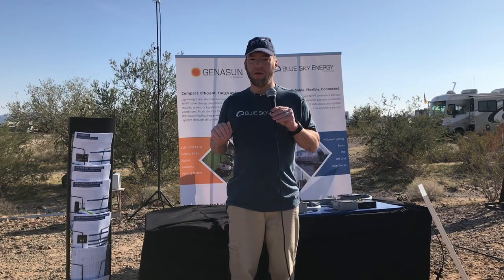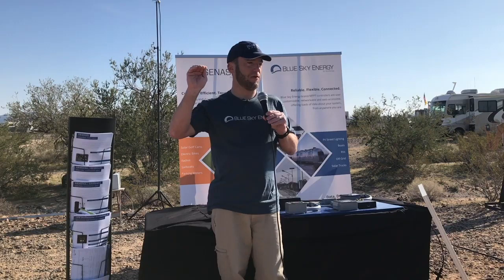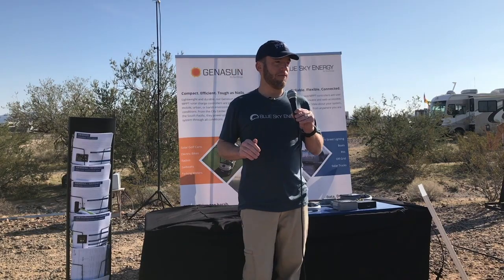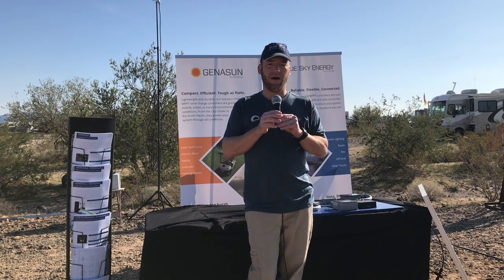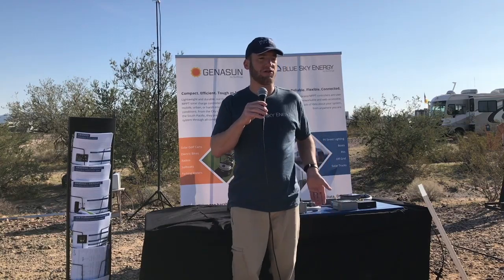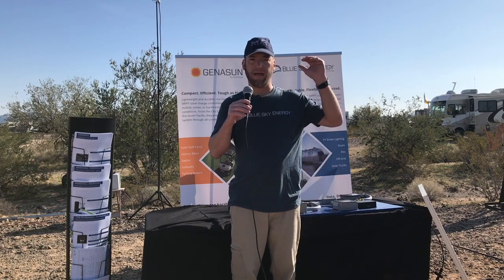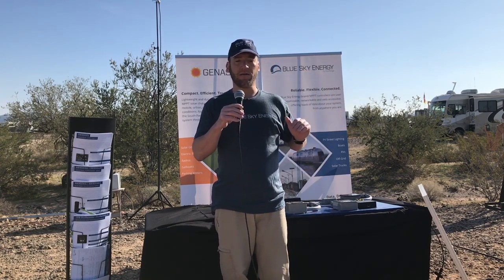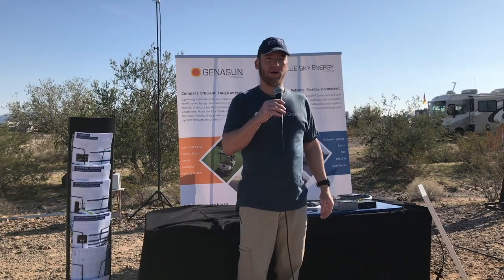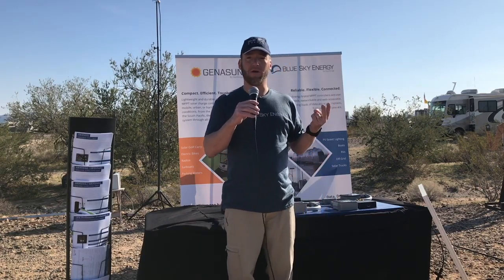That transition from the higher absorption voltage to the lower float voltage can really be done in two different ways. A standalone charge controller doesn't know how much current is reaching your battery, so it's just going to choose a time, or you can program your preferred time for how long it stays in absorption. The ideal time varies depending on how discharged your batteries are - it could need 2 minutes or 4 hours in absorption, really depending on how discharged they were and how long they sat at that lower state.